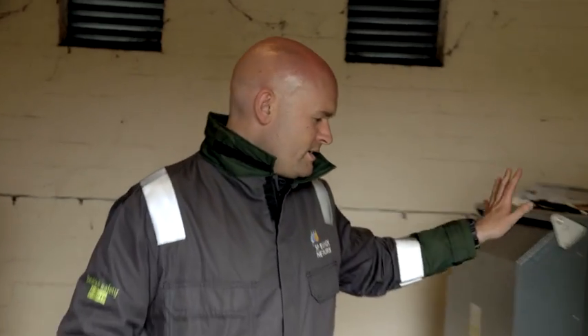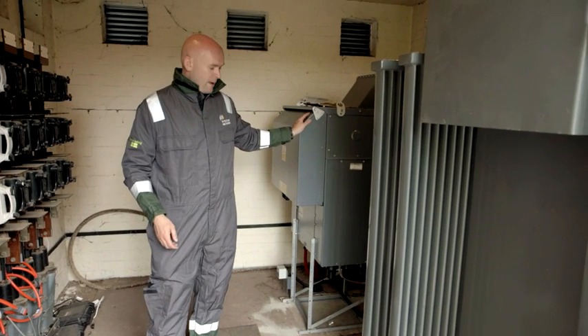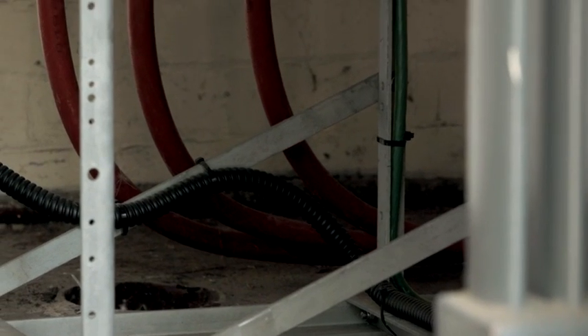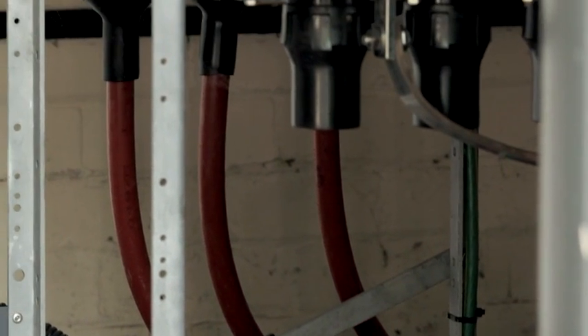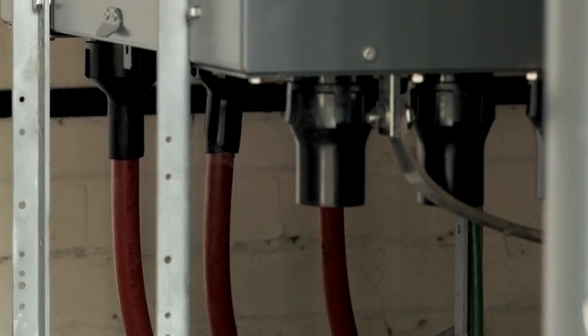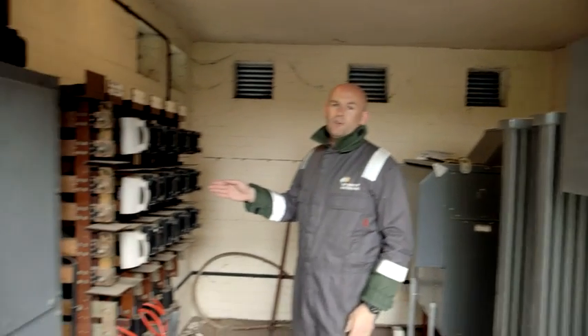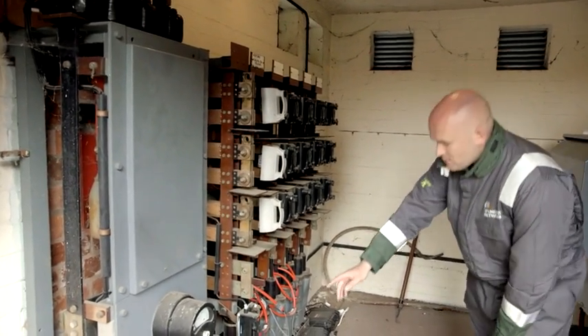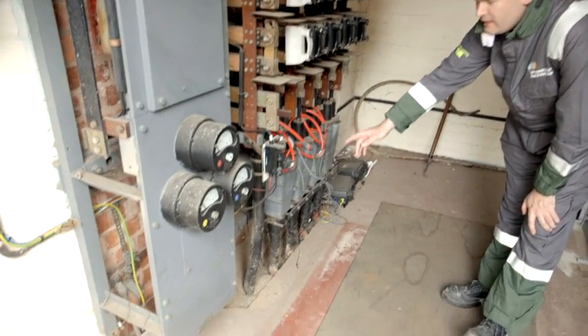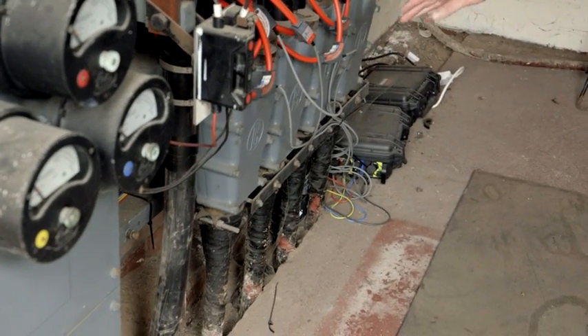This is a typical ground mounted substation. In the corner we've got a switching unit that takes 11,000 volt cables in, you can just see these red ones here. It passes them along to this transformer, which steps the voltage down from 11,000 volts to a lower voltage. And here we have a low voltage distribution board. In this case, we've got 5 cables leaving the board, each supplying an individual street.